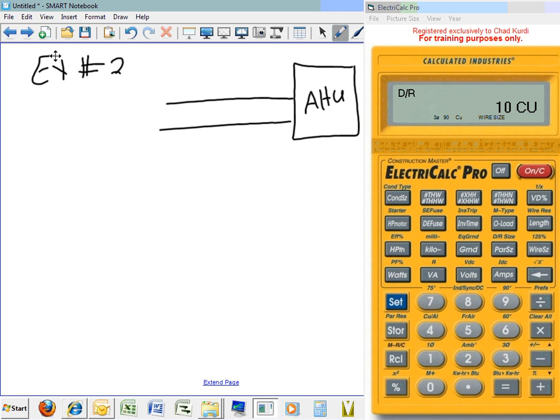So let's grab my panel and come out of here. Here's my panel. Inside this system, I have a 1600 amp circuit breaker, sized it. You know what? Because this is an air handling unit, it's going to change my calculation, because we do them differently. So we don't mess around. We're already messing around here. Let's use this panel, one panel feeding another panel. That would be more appropriate.